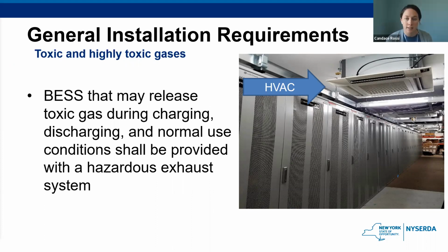Some batteries may release toxic gases during normal charging and discharging. So a forced fan system is used in a battery charging room and other areas where gases can build up in a confined space. This is, for example, a requirement for most lead acid batteries, as they could release toxic gassing during normal operation. Lithium ion does not release any toxic gases during normal operation, and therefore it's not required to utilize this ventilation. Although as we get to the later slides in the presentation regarding thermal runaway protections, you'll see that many lithium ion batteries will install exhaust systems or ventilation, but it's just to meet other requirements in this code and not this one.